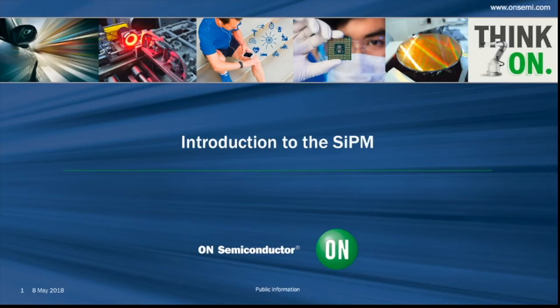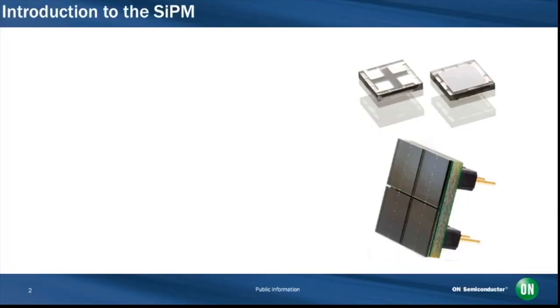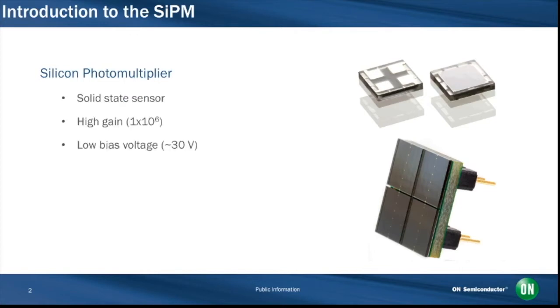This presentation is an introduction to the SIPM. The SIPM, or silicon photomultiplier, is a solid state sensor which has a high gain achieved at low bias. It has single photon sensitivity from the near UV to the near infrared, with a peak detection efficiency of around 50%.